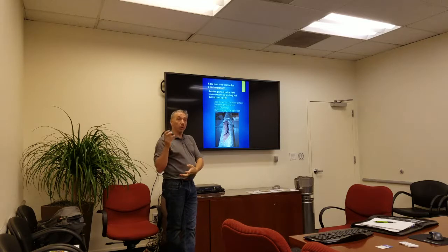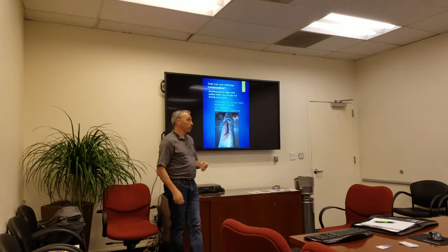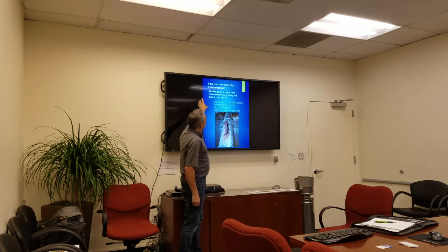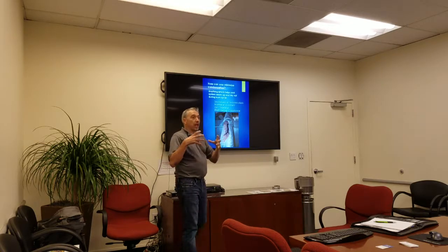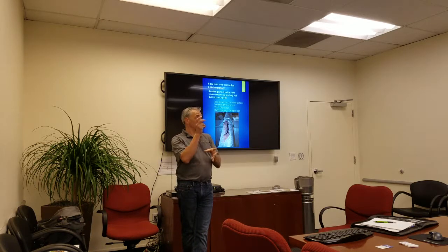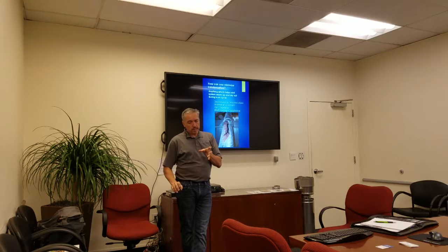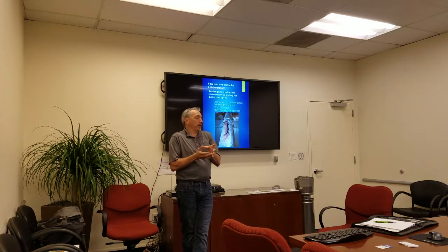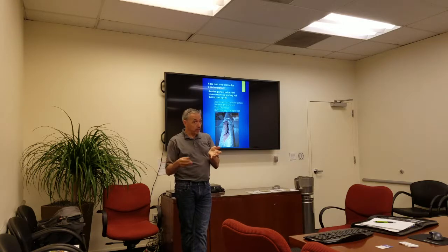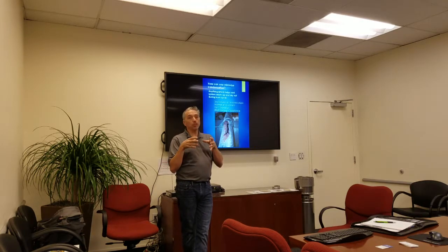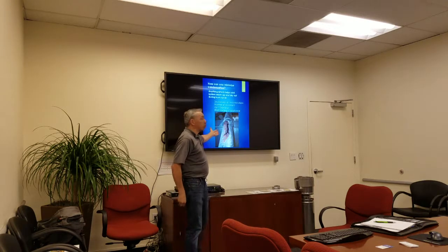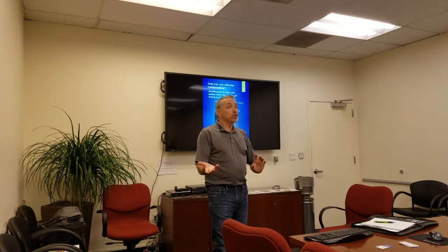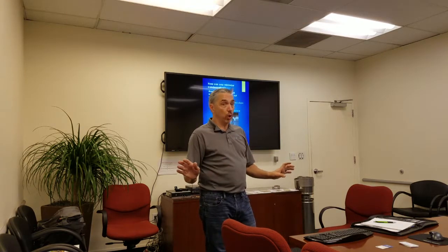The stack system is an integral and important part of any appliance. We can minimize condensation in a couple of ways: we can make the stack warmer by sending more heat up the stack, but that results in a less efficient appliance. Or we can keep our appliance running for a long period of time. If our appliance comes on and runs for 60 seconds and turns off for 60 seconds — called short cycling — the stack will never get hot and condensation will always occur. This could happen in an oversized boiler where the boiler is too big for the load and short cycles because there's no place for the heat to go.